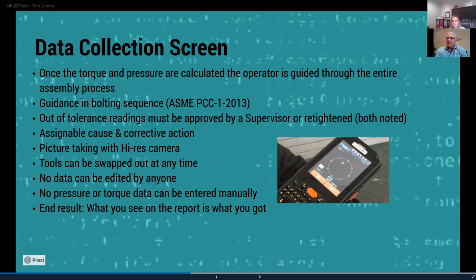No data can be edited by anyone - not by the admin, not by the supervisor, not by the operator, not by me. Nobody can edit the data. And no pressure or torque data can be entered manually by hand; it has to come from the gauge. So you don't have to worry about operators wanting to go home early on a Friday afternoon and just entering the data they're looking for. That can't be done, which is how they can do it today when they're writing it down on paper. This system dictates that it has to come from the gauge, it cannot be edited after that point, and you cannot enter it by hand at all. This means at the end of the day, what you see on the report is what you got.